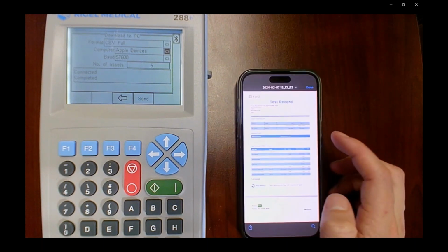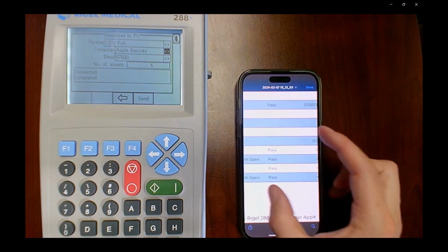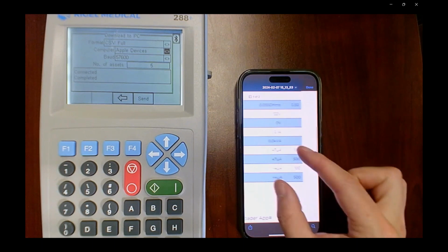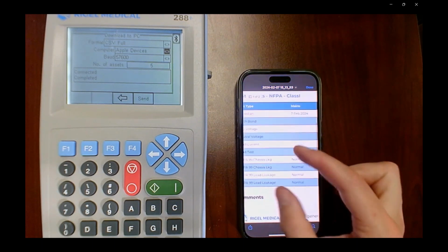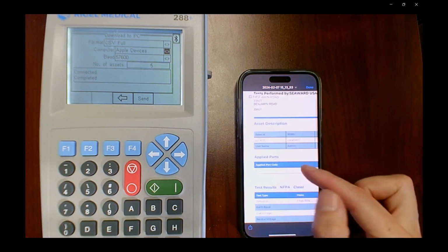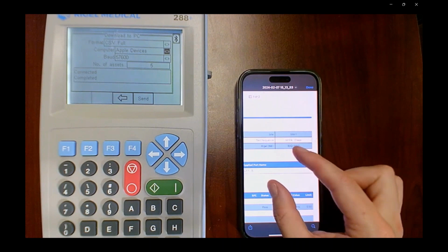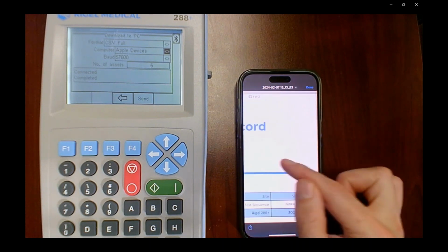and view the PDF. That's the test record. So all the values are automatically input for their status. If the limits are within, then the report gives you a status of passed according to the limits of NFPA 99.